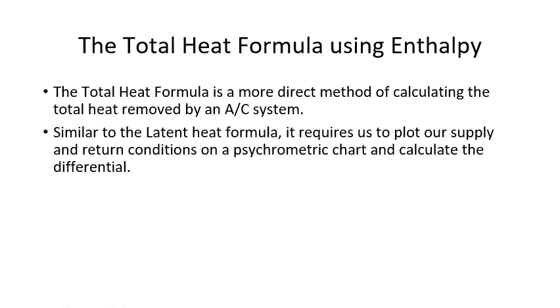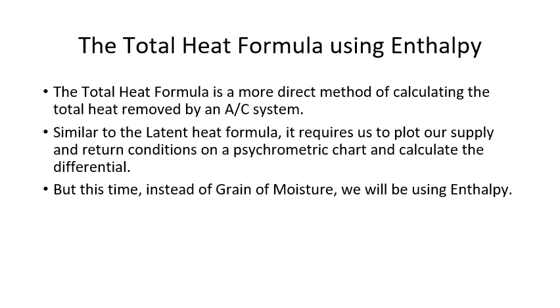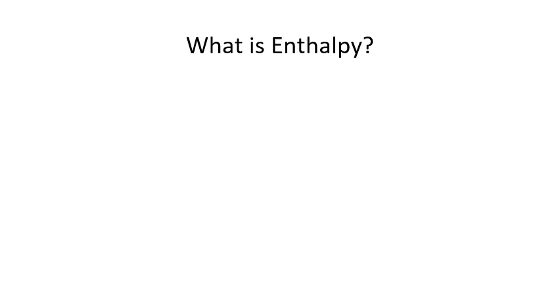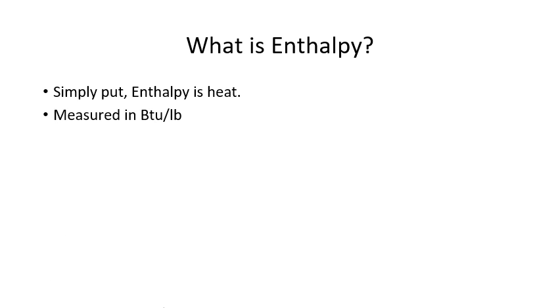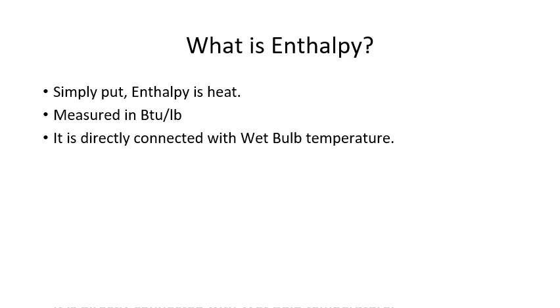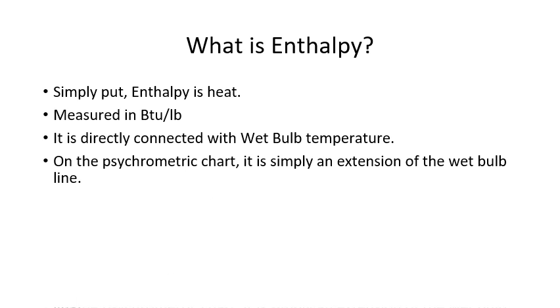Similar to the latent heat formula, it requires us to plot two points on the psychrometric chart, and then instead of calculating grains of moisture, we're actually going to be measuring and doing math to figure out what our enthalpy is. Simply put, enthalpy is the total heat in the air. Its unit of measurement is BTUs per pound of dry air, and is directly connected with wet bulb temperature — enthalpy takes into consideration the moisture level in the air. On the psychrometric chart, it's simply an extension of the wet bulb line.